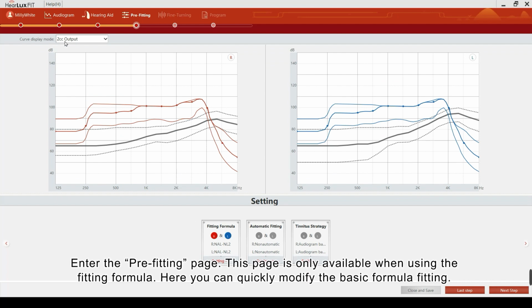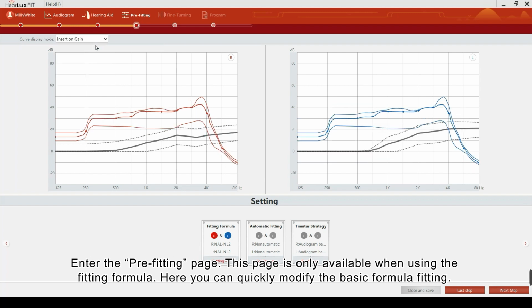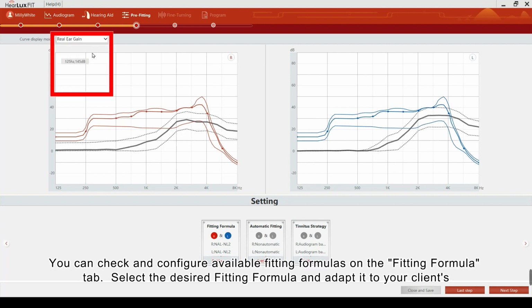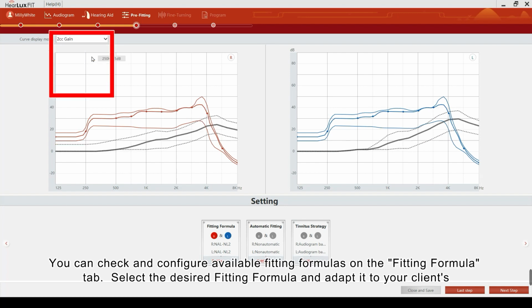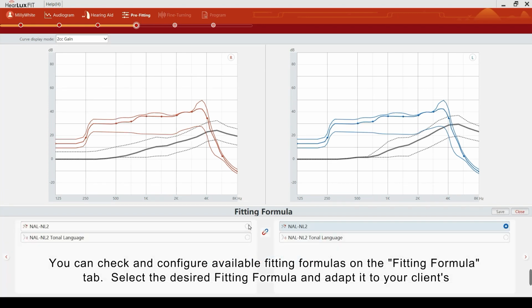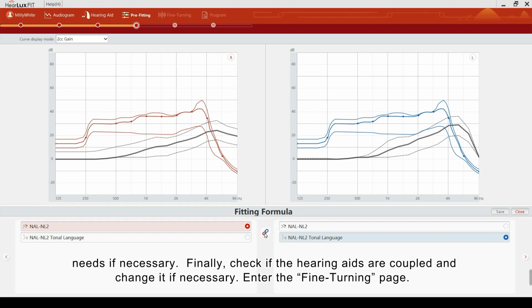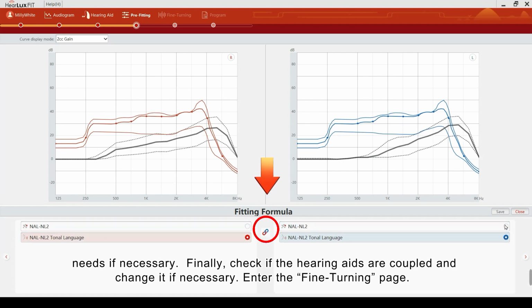Enter the Pre-Fitting page. This page is only available when using the fitting formula. Here you can quickly modify the basic formula fitting. You can check and configure available fitting formulas on the Fitting Formula tab. Select the desired fitting formula and adapt it to your client's needs if necessary. Finally, check if the hearing aids are coupled and change it if necessary.